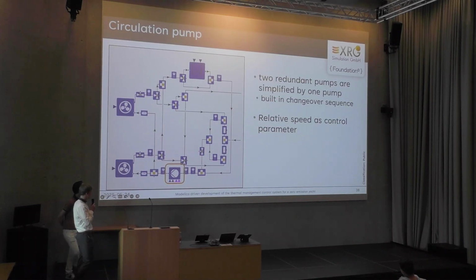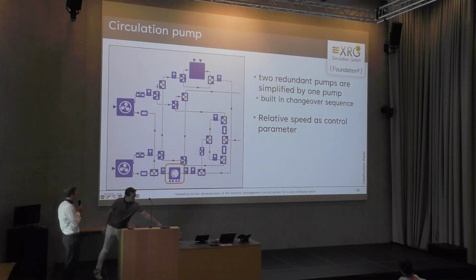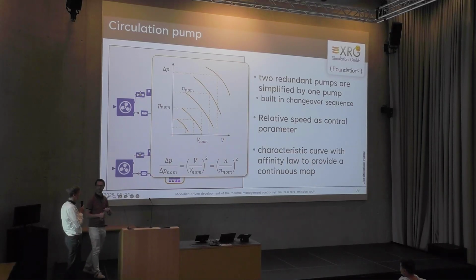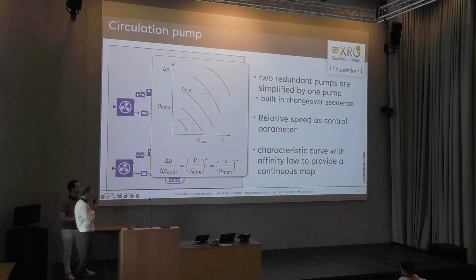On board we have two redundant pumps, but we simplified it to one with a simple changeover built in. We use relative speed as the control parameter, and we give the model some nominal values—pressure head and volume flow—and with the affinity law we provide a simple map for the pump.